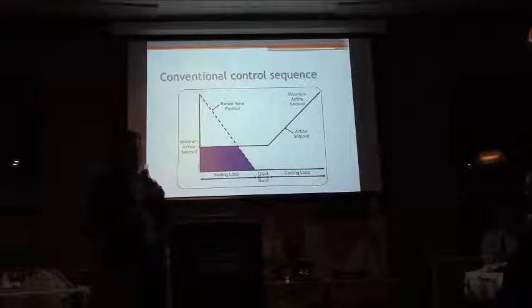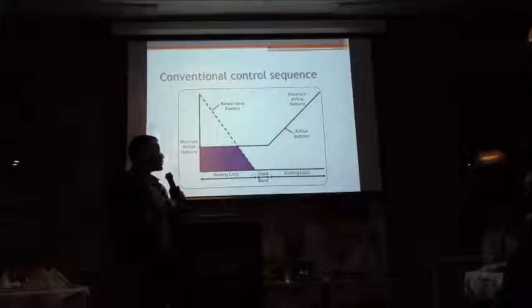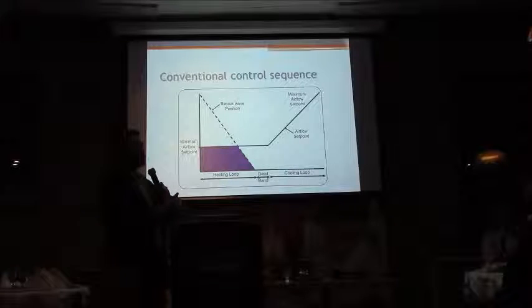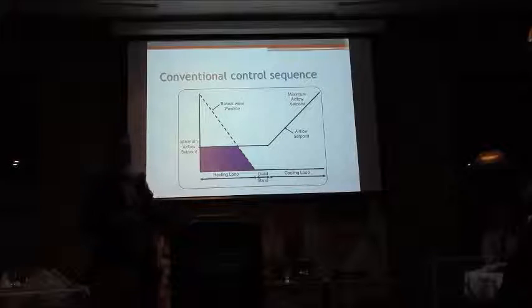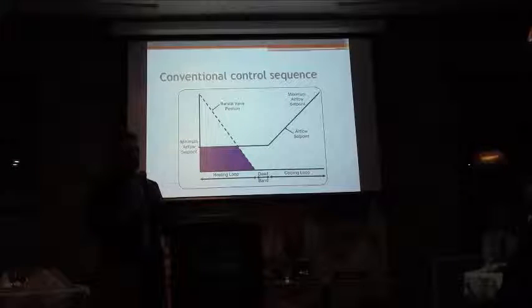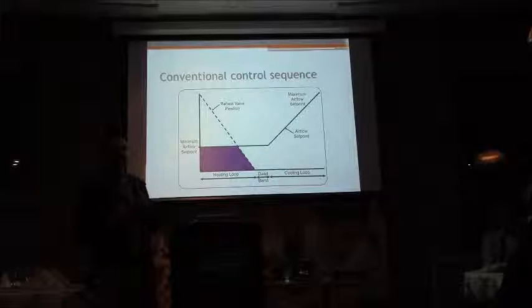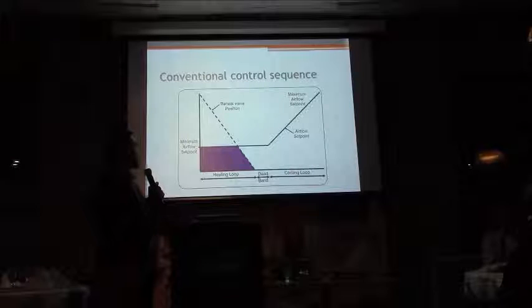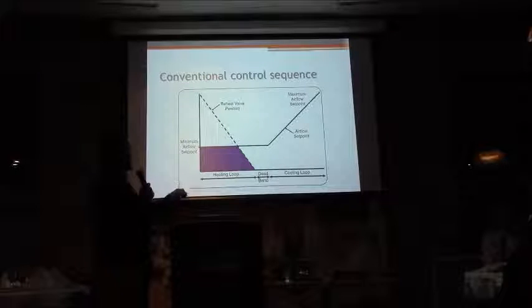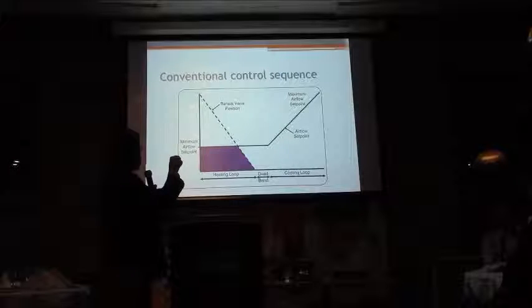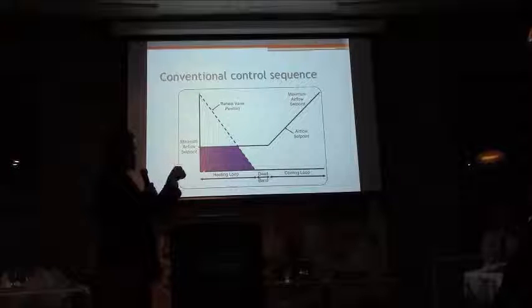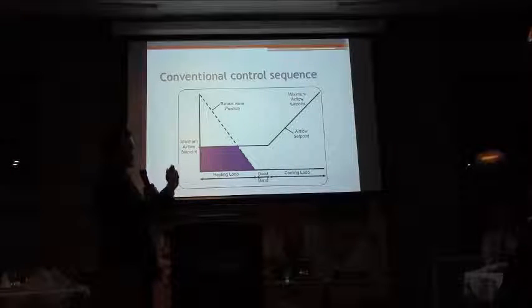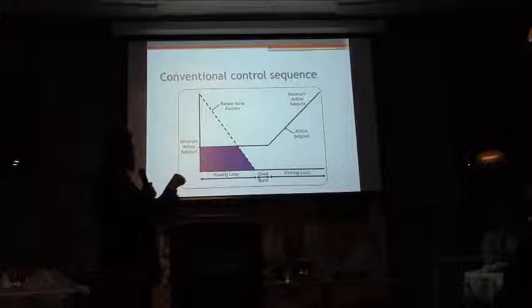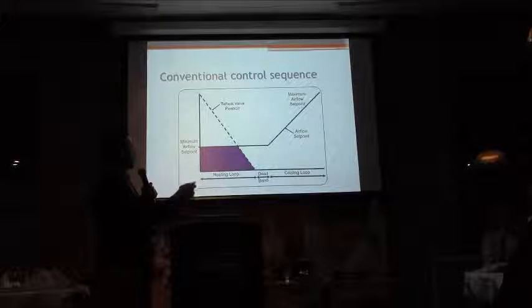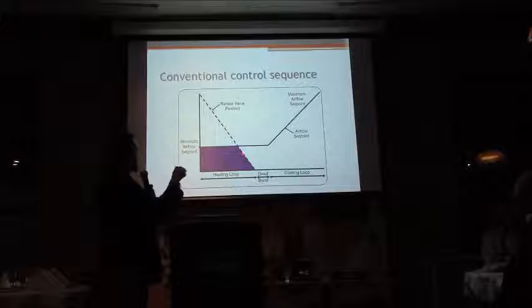I know there are people that might be skeptical, and I have to mention it's not only about the diffuser, it has a lot to do with your control sequence also. So the thing is, when we heat through the diffusers in Canada, the type of control sequence we use is similar to this. The y-axis is basically your CFMs, your airflow, and the x-axis is the temperature of the room. So all the purple area is your heating loop.